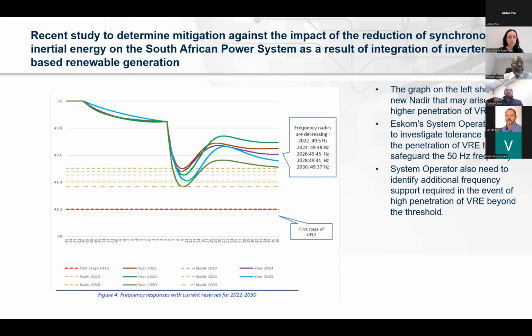So the graph just shows the system frequency. Normal operation started in the frequency deadband, and then we did a big trip on the system, one of the larger generator unit trips, and then you can see exactly what's going to happen to your frequency, how your system is going to respond. For this case, we just depended on the generator governor systems, which basically is the generator control system built into the generator, which will try and arrest the frequency deviations and frequency changes. And as you can see, we can see exactly how that changes with increased renewable energy, or basically for any other event on the system, what the expectation is, how your system is going to respond to that. See if we can go to the next slide.